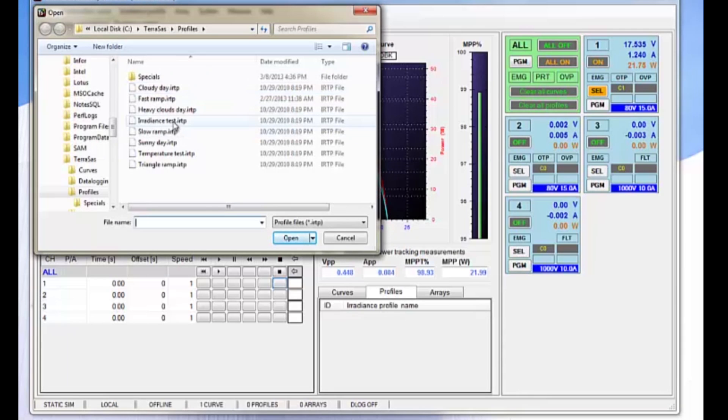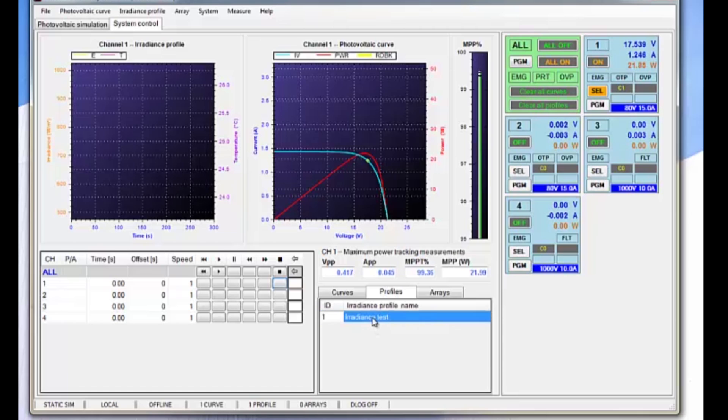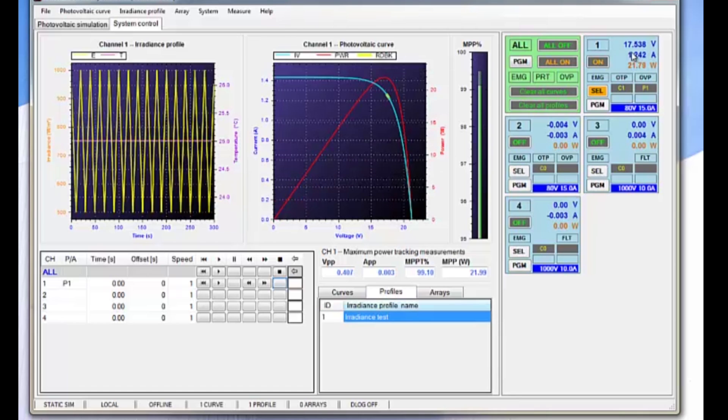Here we're going to import an irradiance test for this demonstration. Then the irradiance test appears in the profiles area. We can then take that and drop it on channel 1, much as we did with the curve profile.